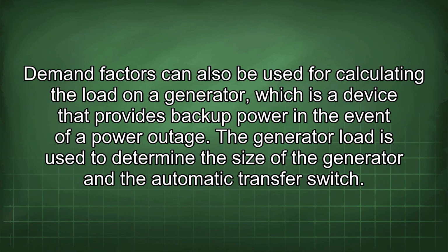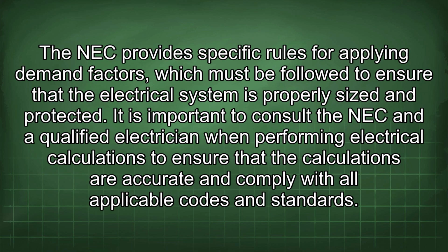Demand factors can also be used for calculating the load on a generator, which is a device that provides backup power in the event of a power outage. The generator load is used to determine the size of the generator and the automatic transfer switch. The NEC provides specific rules for applying demand factors, which must be followed to ensure that the electrical system is properly sized and protected.